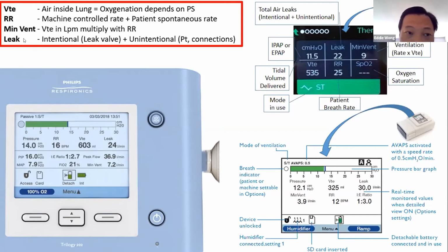And the last one, the leak. You need to understand there are 2 types of leaks. This value cannot be 0. The leak value on the ventilator cannot be 0 because there's always an intentional leak, which occurs when you use a single limb tubing attached to an exhalation valve in order to flush out the CO2. Whatever air flushes out from the exhalation valve, the leak valve, to flush out the CO2, that is the intentional leak.